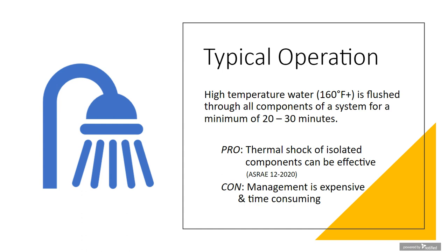So the pros of this is that this thermal shock of the isolated components can be very effective in mitigating Legionella. That's stated in ASHRAE 12-2020. The cons of this is that the management is expensive and time consuming. Now, I don't want to mislead anybody thinking that thermal disinfection is the only mitigation process that's expensive and time consuming. They all are expensive and time consuming. So please keep that in mind, whether it's thermal disinfection, chemical flush, or whatever. It does require a lot of expense and time to fully implement this.